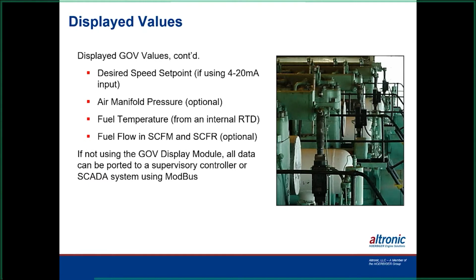Fuel temperature is from an internal RTD in there, and then fuel flow will either read in cubic feet per minute or cubic feet per revolution. So again, that's another device that could be used for calculating horsepower. Again, we talked about if you did not want to use the display and bring it into a PLC of some sort or a SCADA system, you can use the Modbus register numbers to do that.